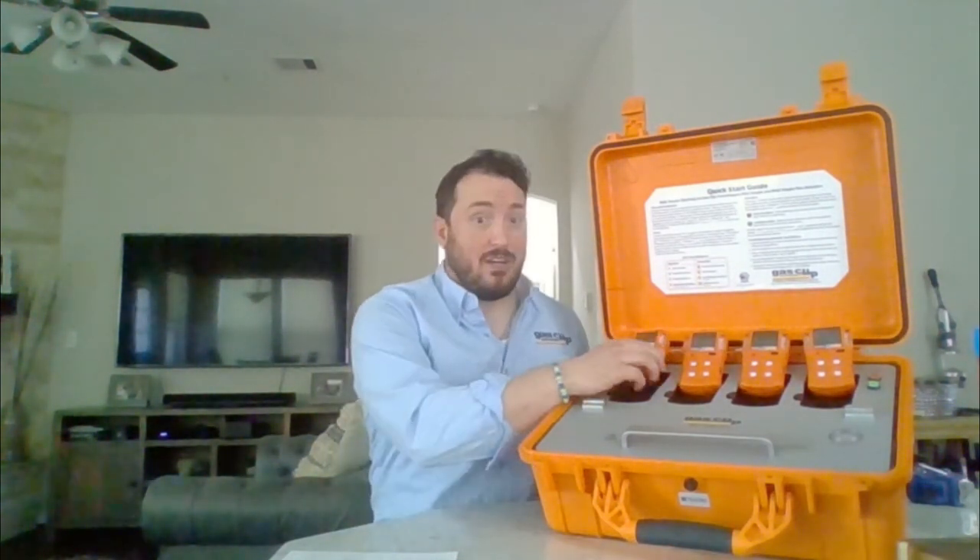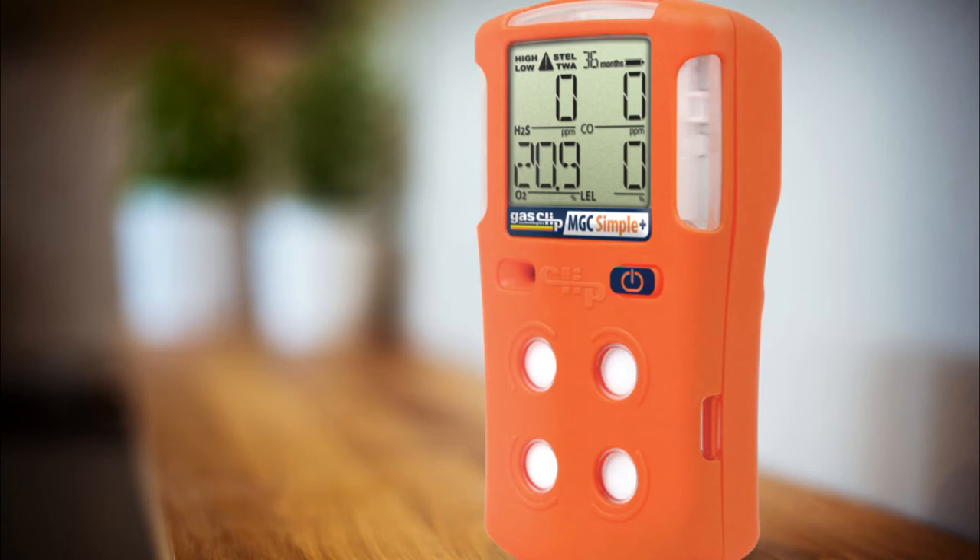Originally gas detectors were produced to detect a single gas, but modern units may detect several toxic or combustible gases, or even a combination of both, which leads me to this. We introduced the MultiGas Clip Simple Plus, or the MGC Simple Plus for short. This unit has four gas sensors to detect H2S, CO, O2, and an IR-LEL sensor. The unit is lightweight — just under a pound — and has an LCD screen to show what the detector is reading, along with bright red alarm lights and sound to let you know when it's going off.